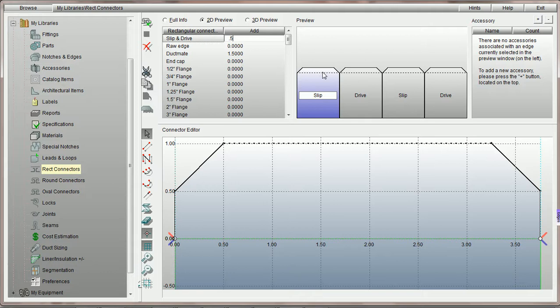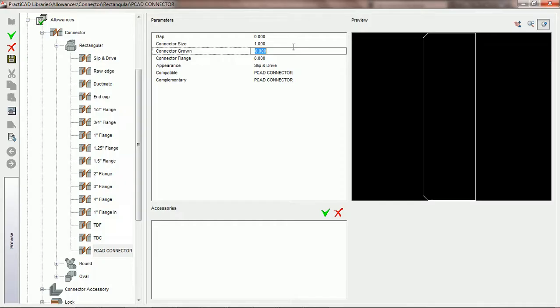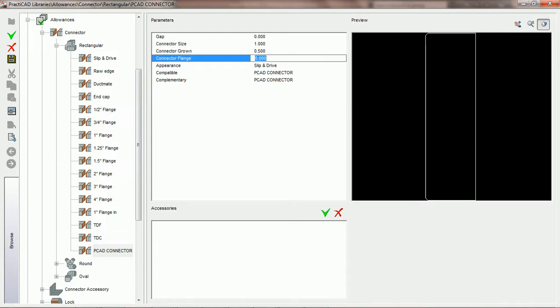For example, with slip and drive, if it's a finished length 5-foot piece of duct or 60 inches, if we lose a 1/2 inch on each side, the finished length for a slip and drive duct off the coil should be 59 inches. The parameter add in PractiCAM is actually the parameter connector grown in PractiCAD. So coming back to PractiCAD, you can see here if we wanted to make a slip and drive, just like we had it in our shop software, we'd make the connector grown a 1/2 inch.